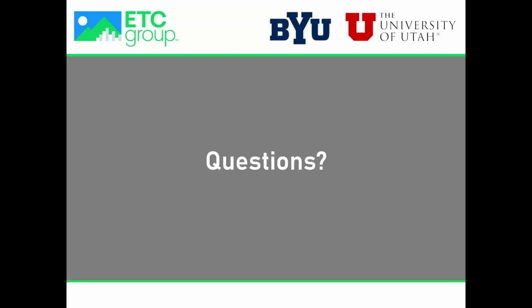We're in the same situation here. A good example of how many faults you can generate is in College of Law. We're fully integrated, and checking occupancy schedules most recently this week, I generated 40 zones that I needed my technicians to look at. If I had an integrated automated system doing that, it would probably generate that every single day, and your technicians would become blind to it, because there's a step you should take prior to sending a technician out—some functional testing or backside checking—just to make sure it's worth sending a technician.